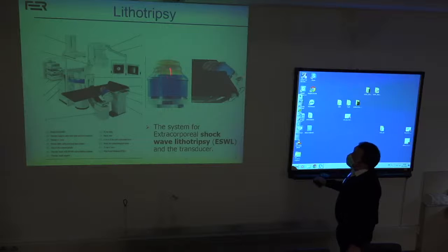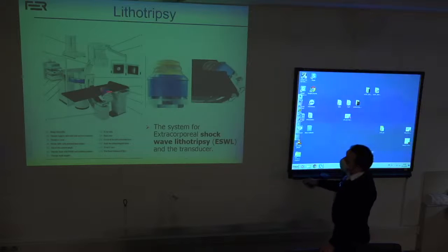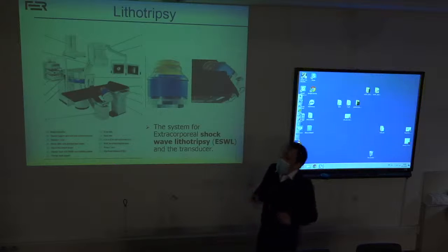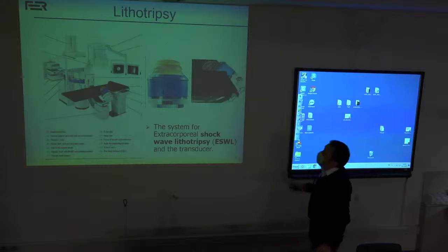Of course, this part may be adjusted in the position. So as you can see on this slide here, it may be also rotated so that the ultrasound wave may target the stones.